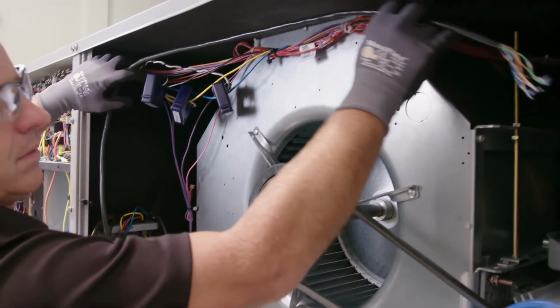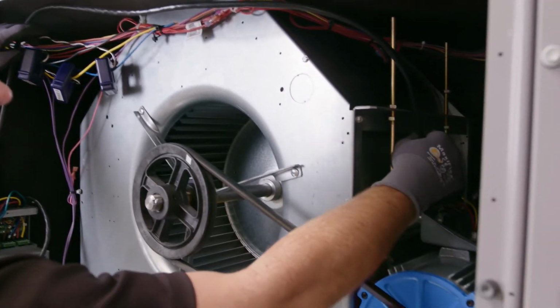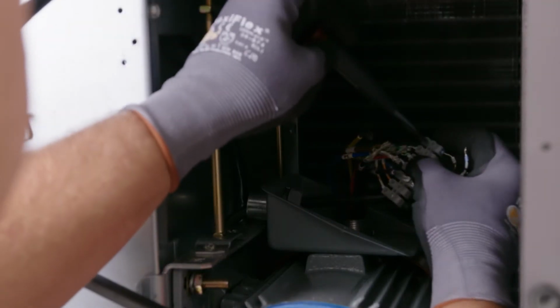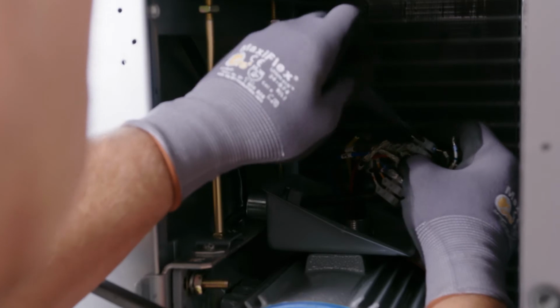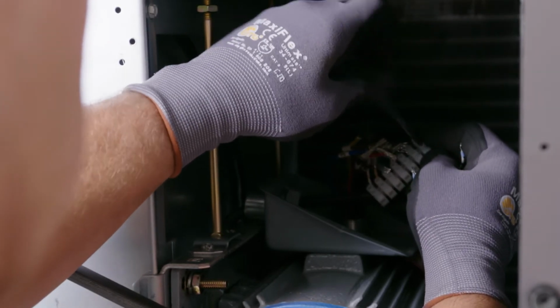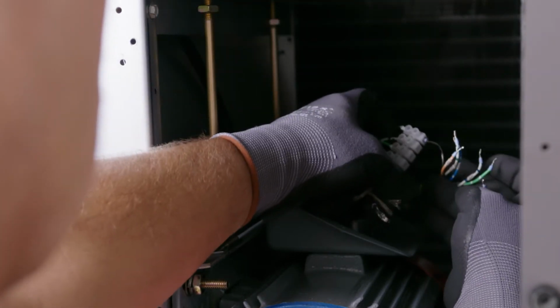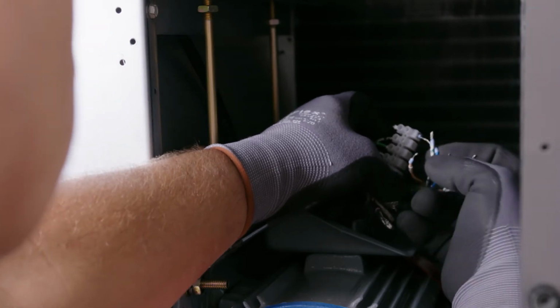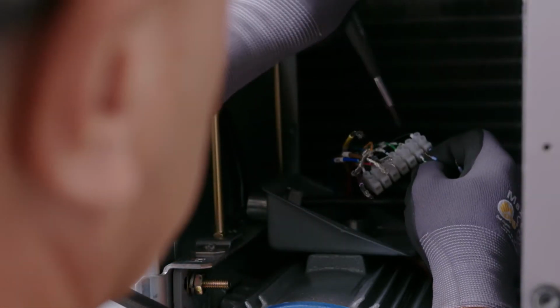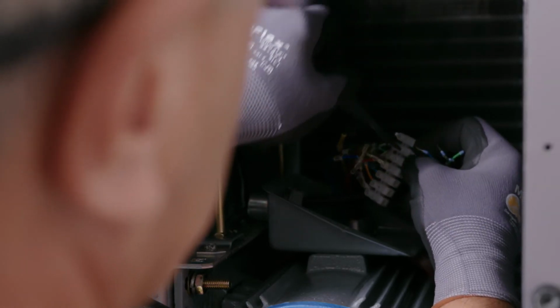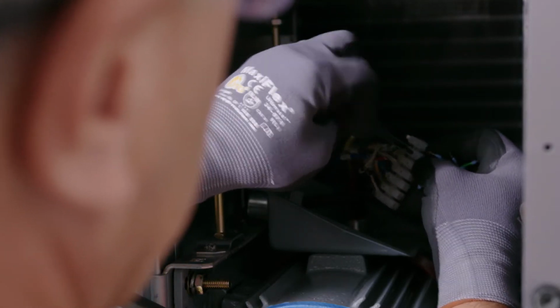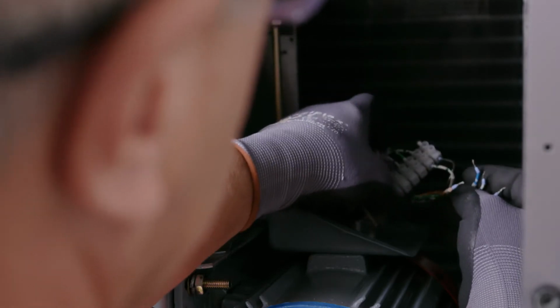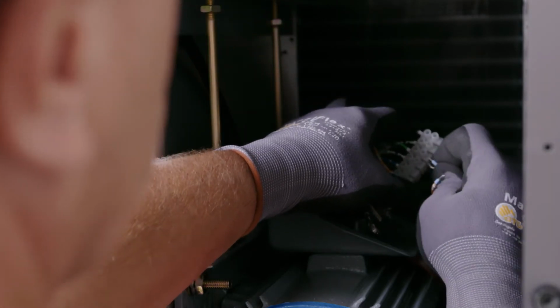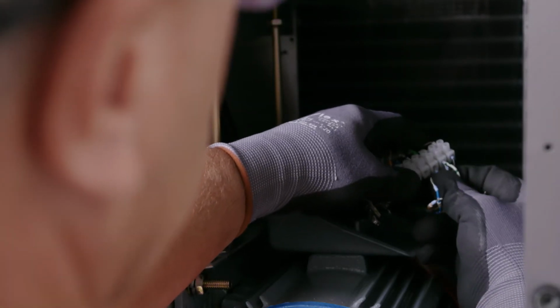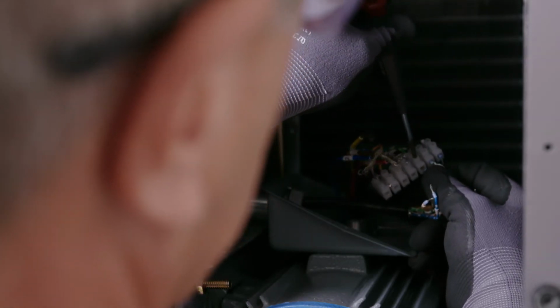The next step is to install the wiring between the smart motor and the motor controller. We'll go over the proper wiring for these cables now. You can also refer to the wiring diagram that's included with the motor. Connect the motor data cable from the motor controller to the smart motor at the motor junction box. The motor data cable is labeled D1 through D7. This cable has 7 leads on one end and 6 on the other. The side with 7 goes to the motor, the side with 6 goes to the motor controller. Whenever you have questions, simply refer to the wiring schematic.